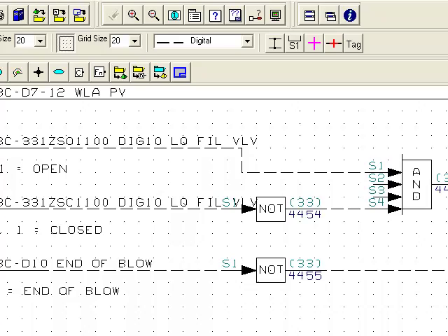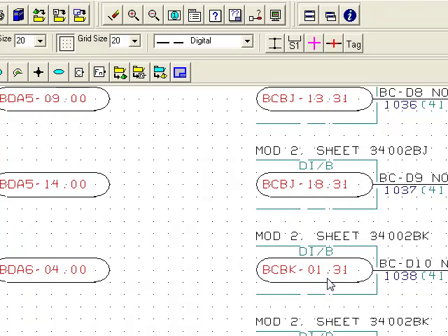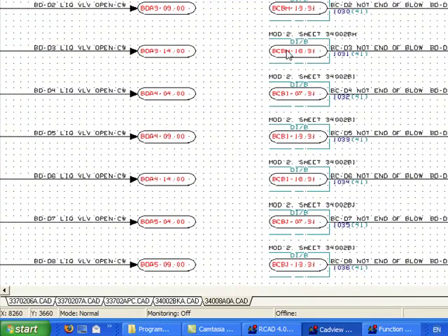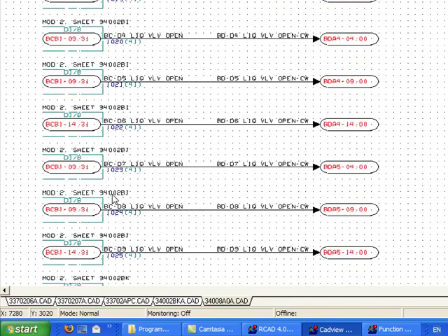Now these types of function codes, these function codes 41, 42, 25, 26, 63, 64, those are the commonly used ones for bringing in signals from other modules, either inside the same PCU cabinet or in a different PCU cabinet, or on a different PCU cabinet in a different loop, using function codes 121 and 122.